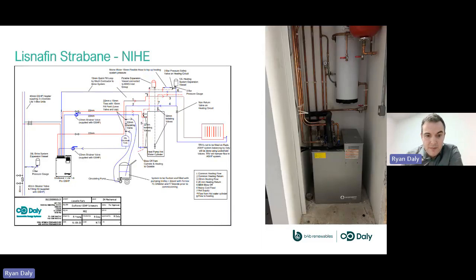That's a schematic there of what we've done in terms of the fitting of the heat pump. And we have the EcoGeo Lite, the 1 to 6 kilowatt on the ground source. One of the things we recommended was no TRVs fitted on the radiators. We didn't want TRVs short circuiting the heat load going through the radiators. So it's better to balance your system and have your radiators balanced correctly rather than relying on TRVs. And it just means that there's more volume in the system when the heat pump does come on. It's not heating one radiator, it's heating all the radiators in the flat.